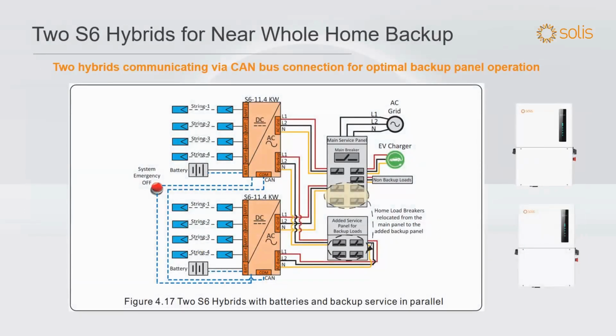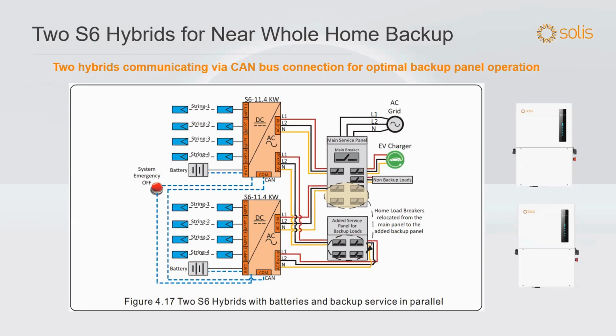I know this is a bit more complicated than those single lines, but I wanted to show you this because here we're talking about two inverters in parallel at the main service panel. You've pulled out some loads into a backup panel, and paralleled the output of the two inverters into that backup panel. You can be as much as 100% unbalanced, all 120 loads, that sort of thing. These inverters really coordinate their activity to that backup panel because of the CAN bus connection between them. It's kind of a gross way to control your inverters these days, but we can hardwire these inverters together and they'll work as one for that backup panel.